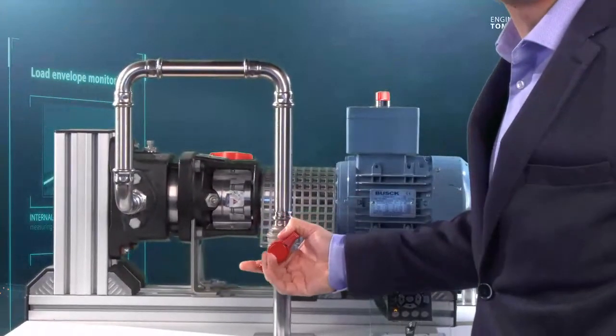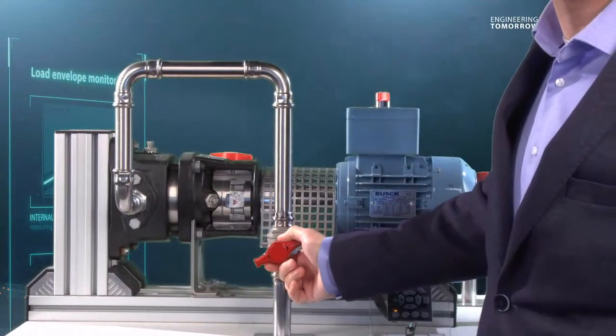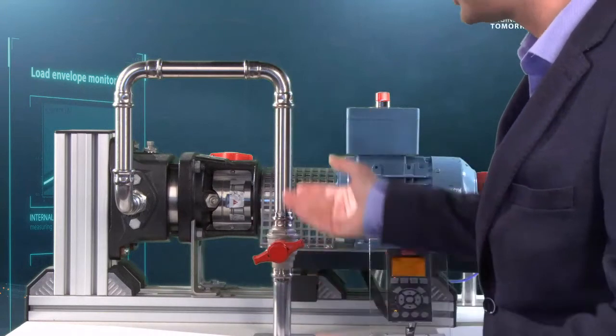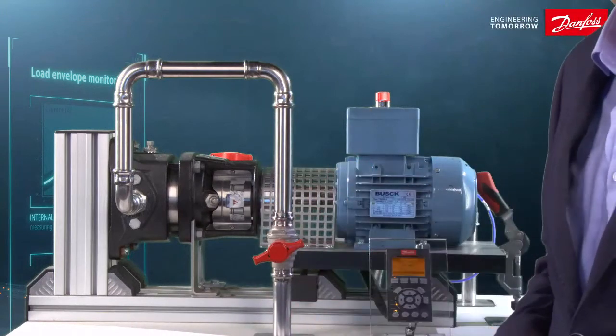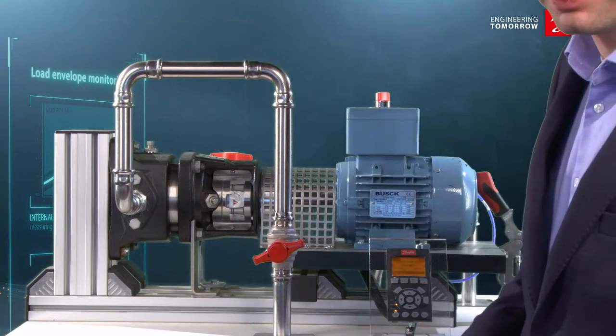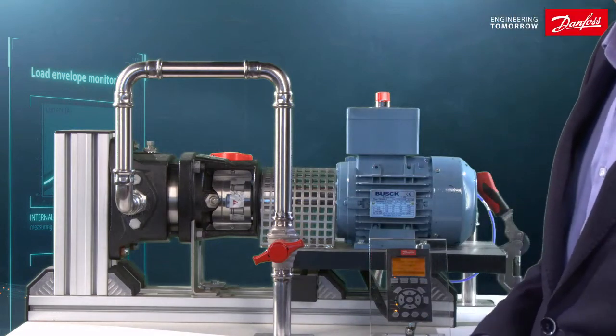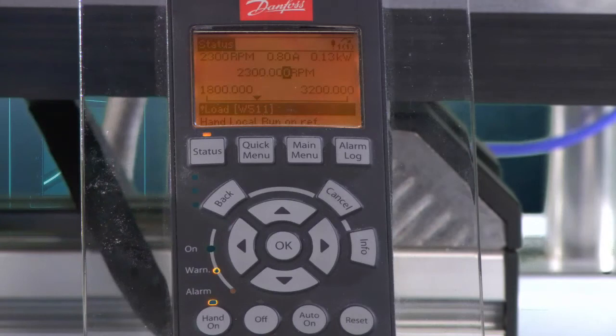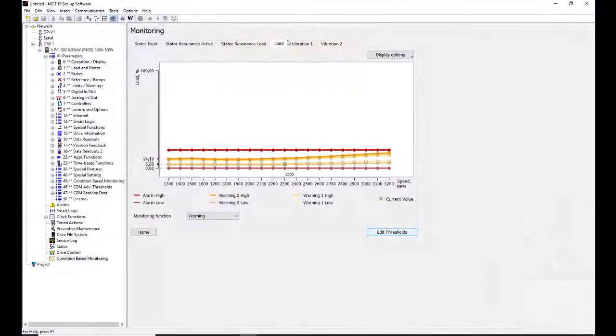And now I simulate a fault in the flow. I change the flow of water here, simulating, for example, that the pump is running heavier, and this is again detected by the drive, and I get a load warning. At the same time, you can also see in the graph that the level has exceeded the threshold. Now I remove the fault, and the application comes back to the normal level.